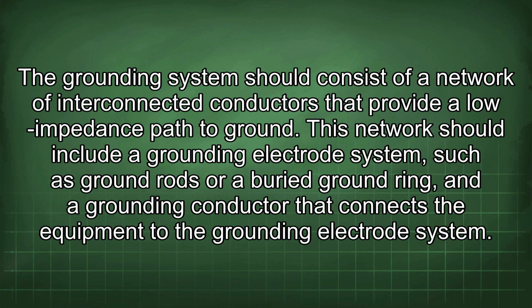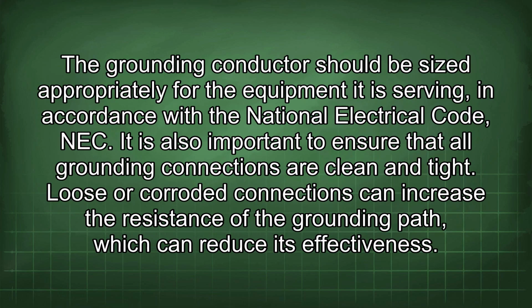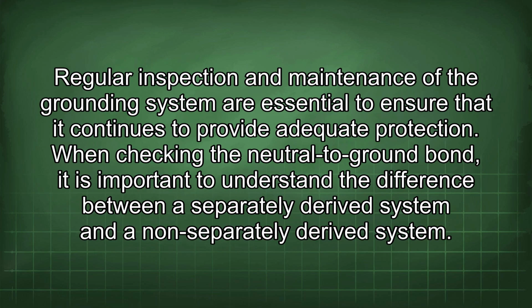The grounding system should consist of a network of interconnected conductors that provide a low impedance path to ground. This network should include a grounding electrode system, such as ground rods or a buried ground ring, and a grounding conductor that connects the equipment to the grounding electrode system. The grounding conductor should be sized appropriately for the equipment it is serving, in accordance with the National Electrical Code, NEC. It is also important to ensure that all grounding connections are clean and tight. Loose or corroded connections can increase the resistance of the grounding path, which can reduce its effectiveness. Regular inspection and maintenance of the grounding system are essential to ensure that it continues to provide adequate protection.